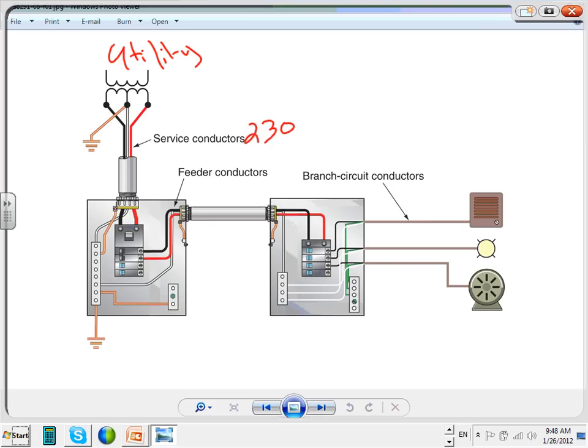And then when you take a feeder from the service, this is my service panel, you take a feeder from the service panel into another panel, that becomes a feeder, and this is covered by Article 215 in the NEC code book. And then you take a branch circuit, and that's covered by Article 210. So these are, guys, 3 important circuits covered by the NEC, and we use them in every type of building that we have, single phase or 3 phase. Does that make sense? Utility transformers bring the conductor, single or 3 phase, through a conduit to the service panel. From the service panel, you go to another panel, that's called a feeder. From the second panel, you go to the last utilization equipment, that's called the branch circuits.